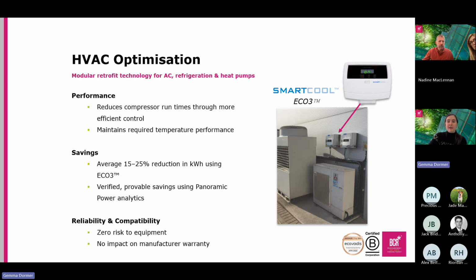By closely managing the compressor operation - because fundamentally compressors are just pumps - it achieves a 15 to 25% reduction in energy consumption. This particular system, the Eco3, has verified demonstrable savings. It's been installed in about 35,000 sites, and has been tested using the panoramic power system that Rich mentioned, to validate the performance.